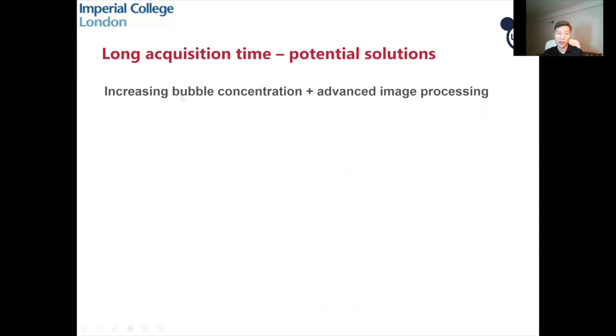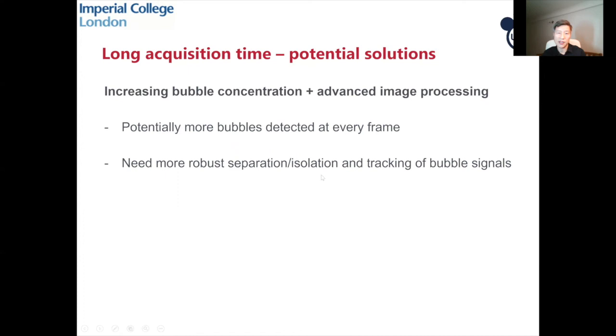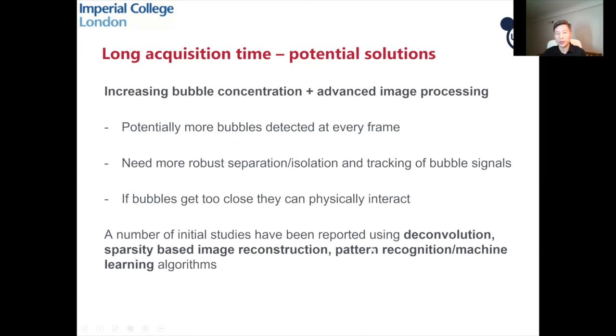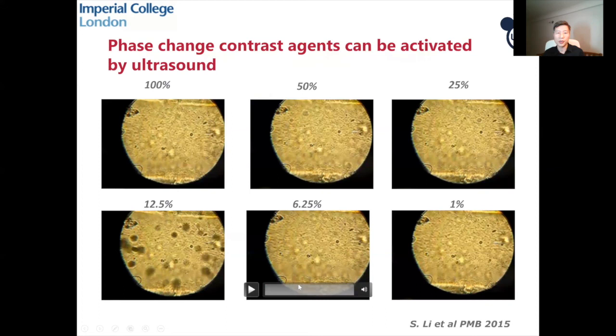For the long acquisition time challenge, one possibility is to increase bubble concentration and then use advanced image processing to handle that — potentially more bubbles detected per frame, requiring fewer frames and less time. But this needs more robust signal processing to separate, isolate, and track the bubble signal. If bubbles get too close, they can even physically interact, which is another challenge. Initial studies have used techniques like deconvolution, sparsity-based image reconstruction, pattern recognition, and machine learning algorithms to deal with higher concentration situations.